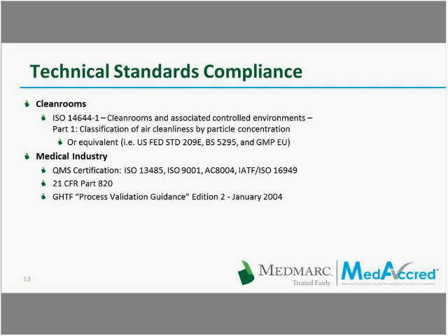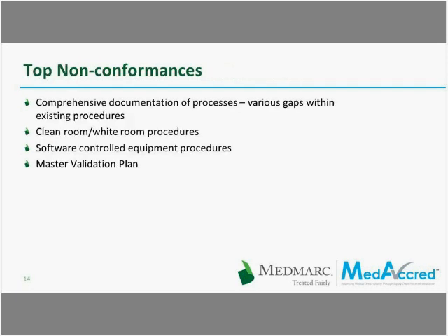So what are some of the top non-conformances that we run into as we are conducting our audits? Well, I think really the top non-conformance we run into is comprehensive documentation of processes. We never go into a facility, you should never say never, you should always avoid always, but nevertheless, I think we never go into a facility that doesn't have lots and lots of processes documented. But what we often encounter is there are some gaps that exist within all of those procedures. Or sometimes those procedures don't link together well. Sometimes it's even a surprise to the people that are being audited that they had somehow failed to have that particular documentation in place. One of the areas, especially for that, is in clean room and white room procedures. We often see some gaps in that area.